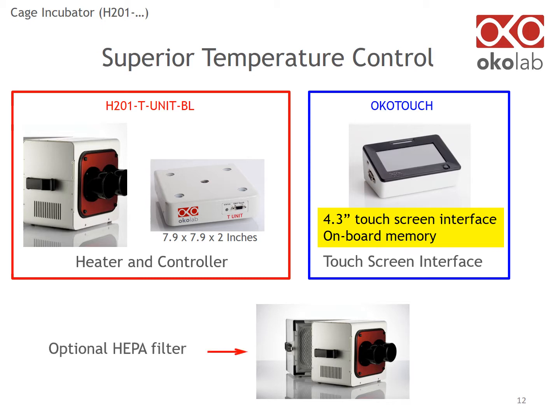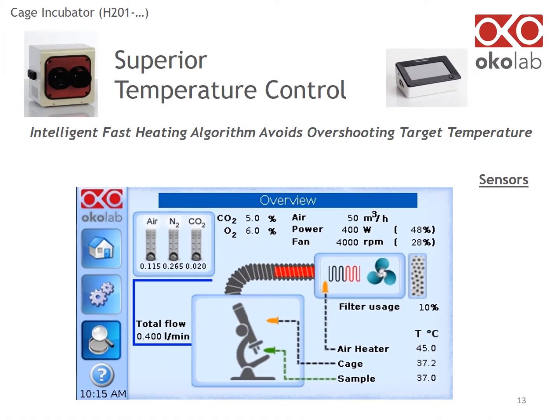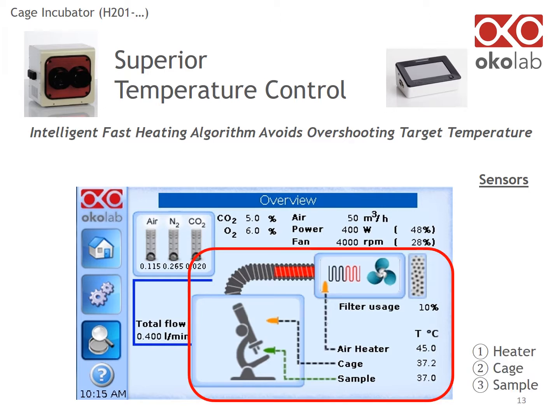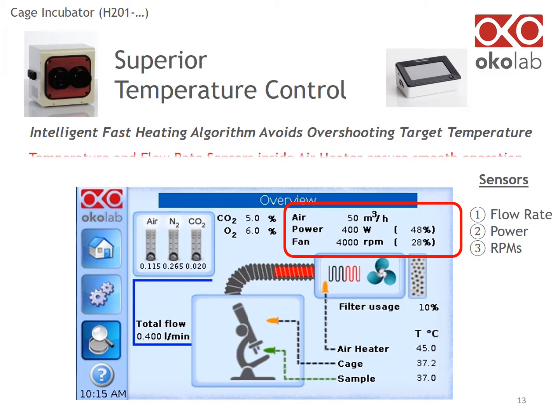The heater can be equipped with an optional HEPA filter. The heating system is equipped with sensors monitoring the temperature inside the heater, the cage, and the sample. Additional sensors monitor the airflow, power of the heater, and speed of the fan. All data is processed by the OkoTouch algorithm, which adjusts each component, ensuring smooth operation and avoiding overshooting the target temperature.